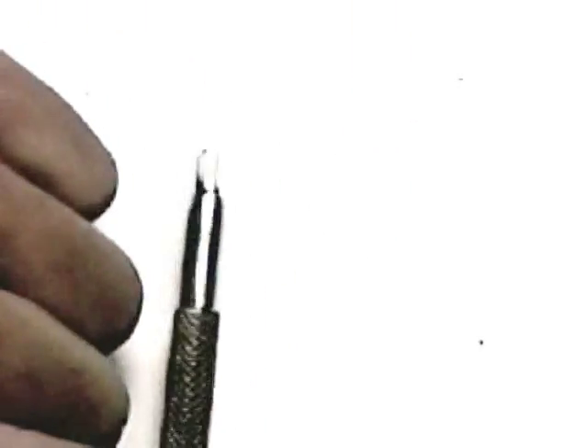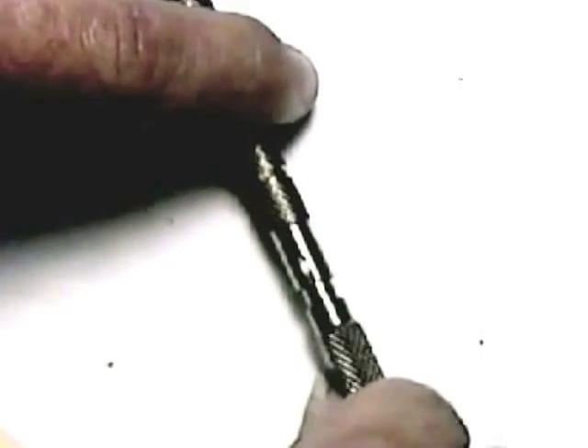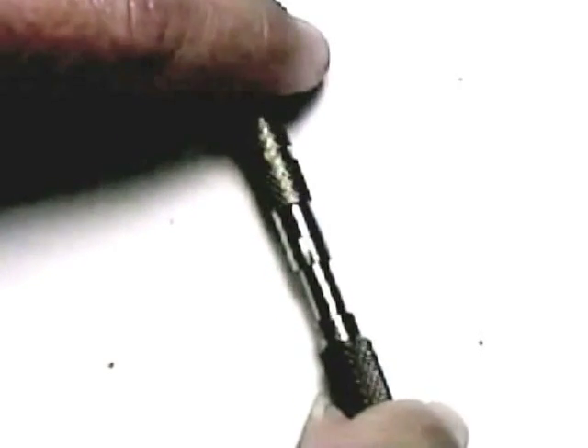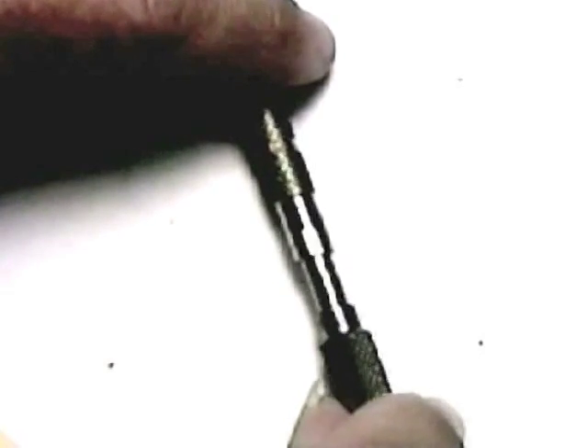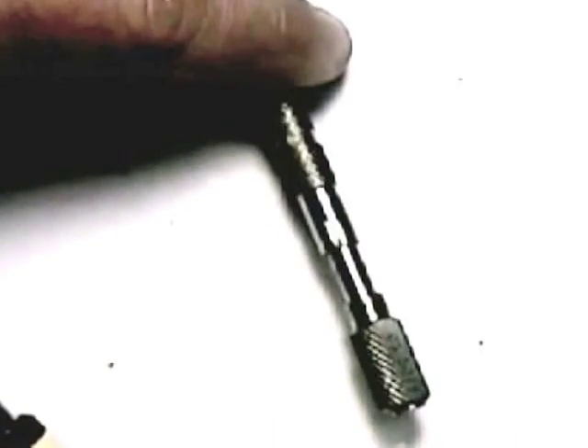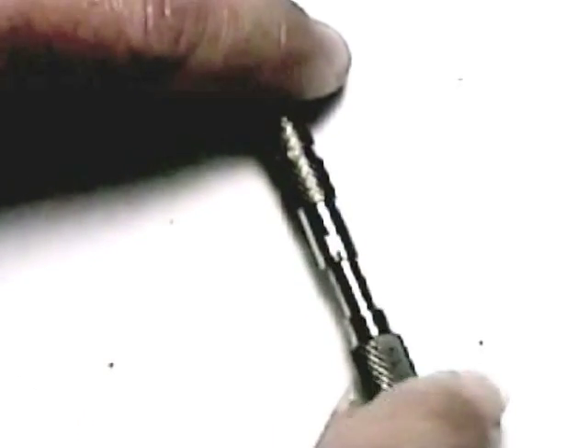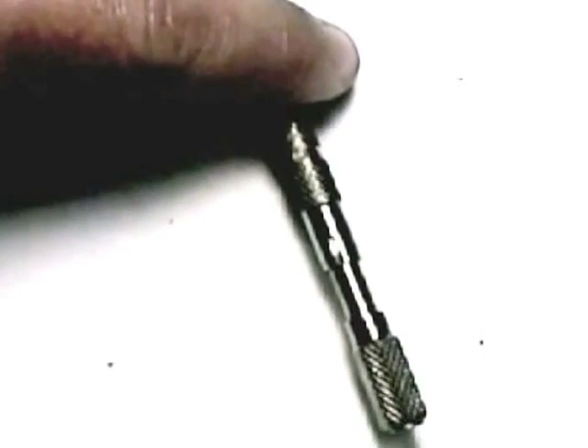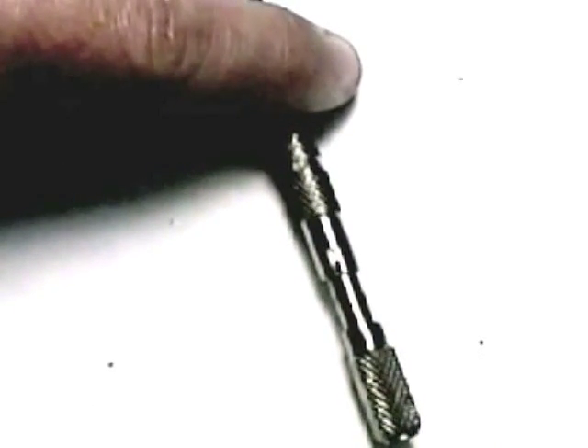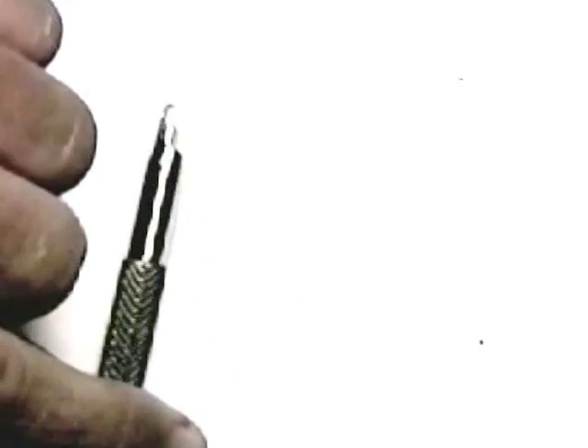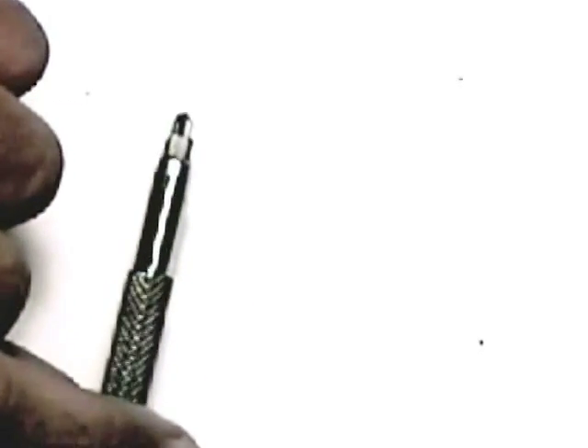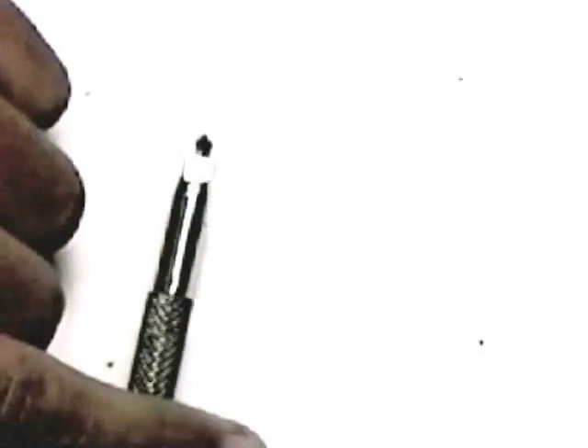Likewise, when you turn this to 0.3, that would be a 300 micron extension, 0.4 would be a 400 micron extension, and 0.5 would be 500 microns or 0.5 millimeters of extension beyond the foot plate. And that is presented here. You can see the blade extending beyond the foot plate, in this case 500 microns.